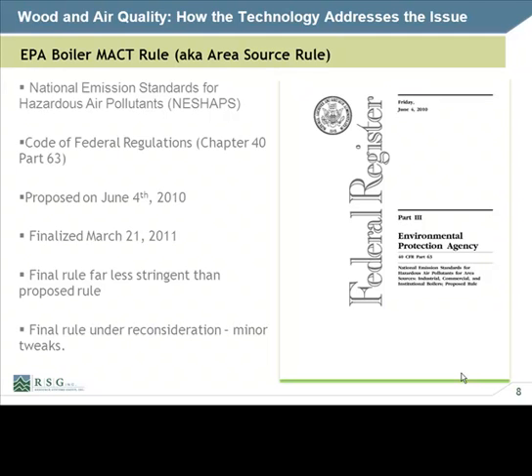That's a very strict standard, and it applied to all boiler sizes. At the end of the day, the economy tanked, industry pushed back, everybody pushed back, and we wound up with a final rule that's a lot less stringent and more flexible. That particulate limit was increased up to 0.07 pounds per million BTU, effectively doubled, and it only applies to large boilers, those with heat input greater than 10 million BTU an hour.